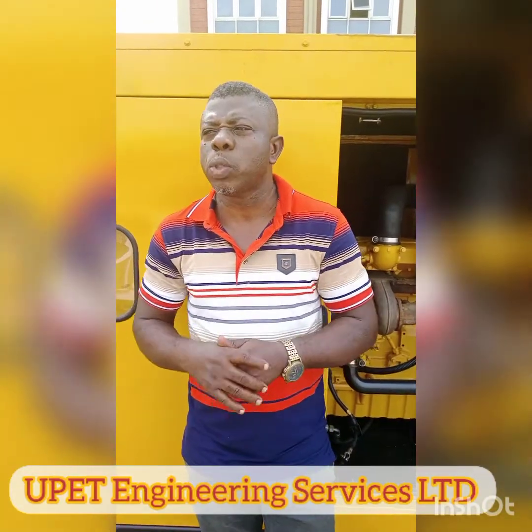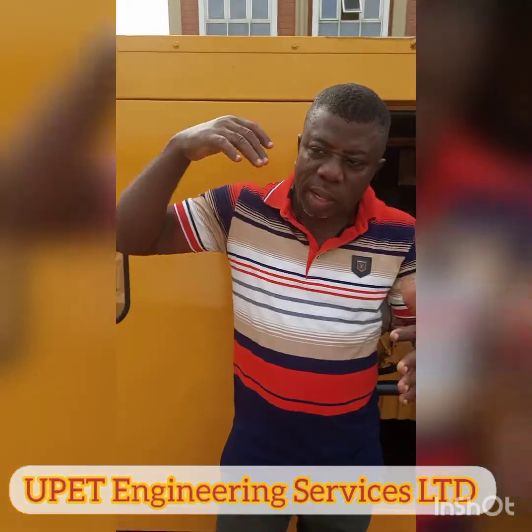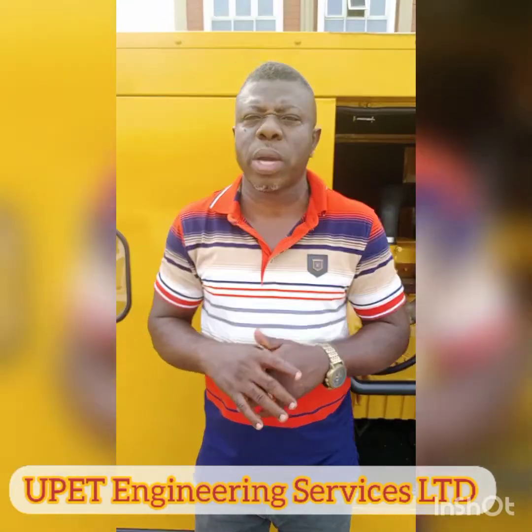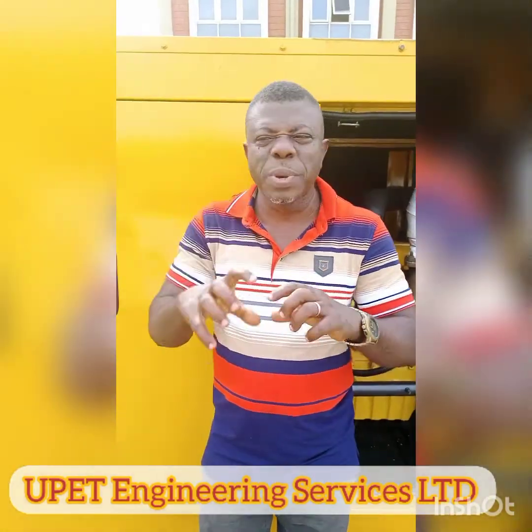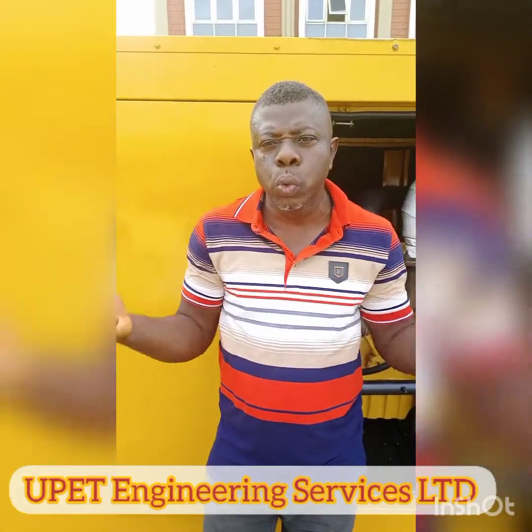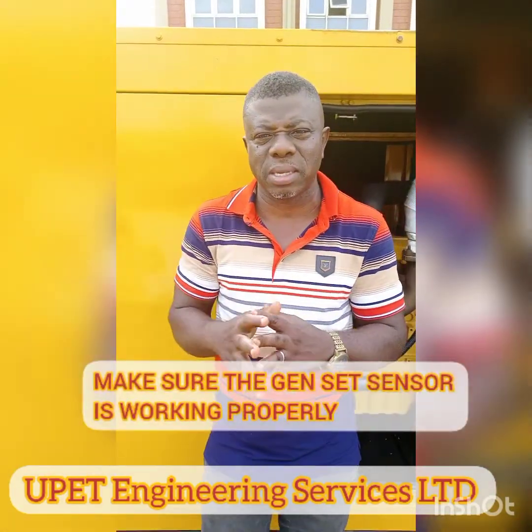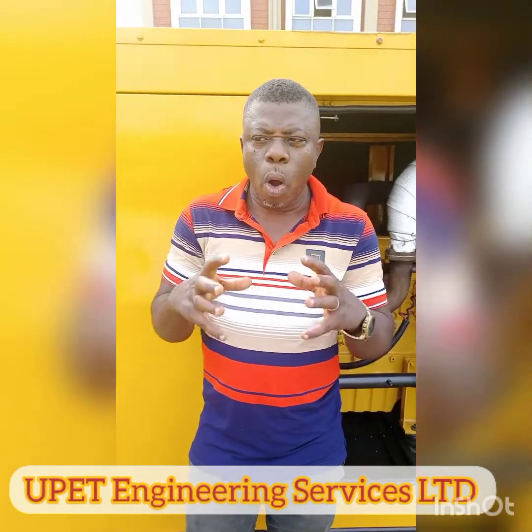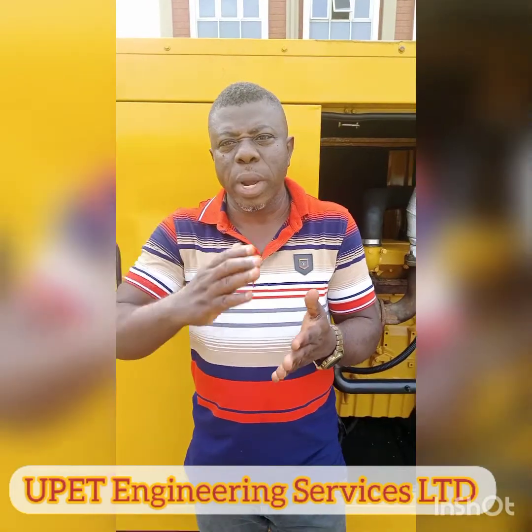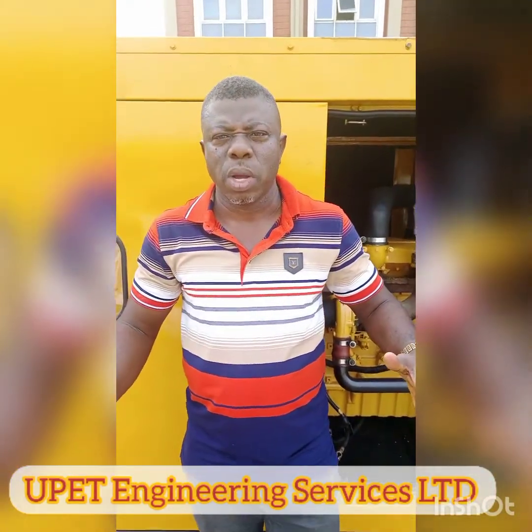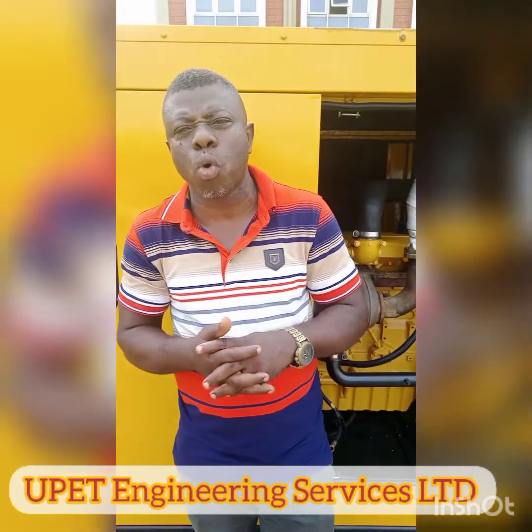And also, I want to talk about the overheating switch, or you can call it an alert. We have a sensor that is called a temperature switch. That temperature switch is connected to the module, that's the panel of that genset. Its work is that once the temperature goes beyond 70 to 80 and is entering 90, the generator will definitely shut down, if the sensor is working properly.